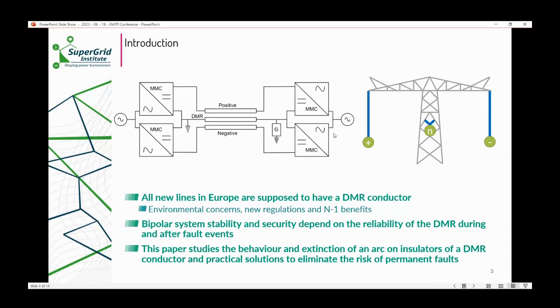It's important to say that in normal operation, positive negative pole currents are almost perfectly balanced, so the current through DMR is zero and voltage drop across the DMR is close to zero. But in case of a monopolar operation, the full current goes through DMR, so the voltage is equal to the voltage drop along the conductor. Bipolar system stability and security depends on the reliability of DMR during and after fault events, so in case of a fault on either of the poles, we need to keep DMR operational.